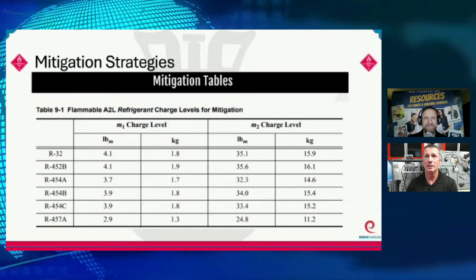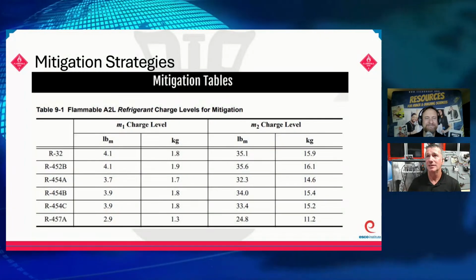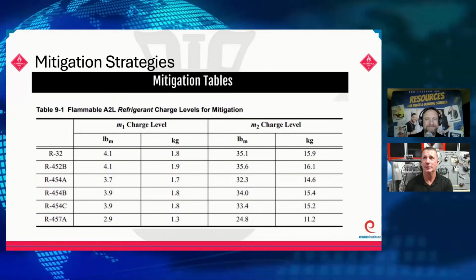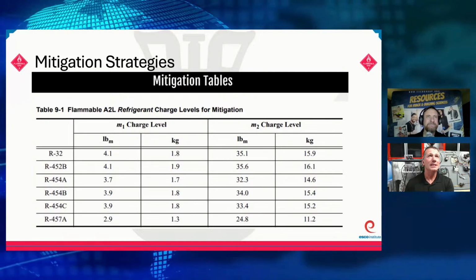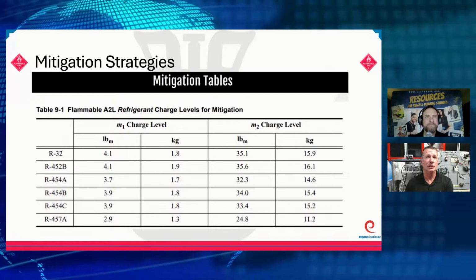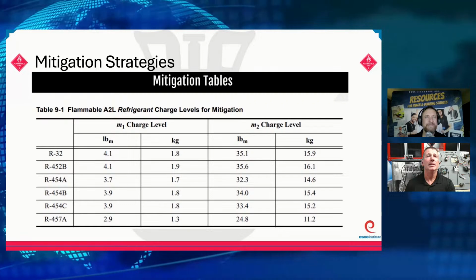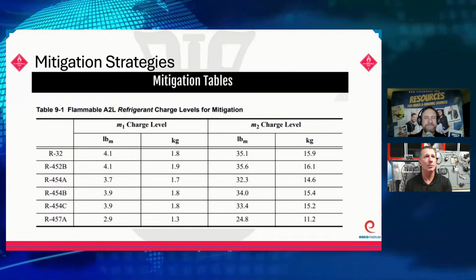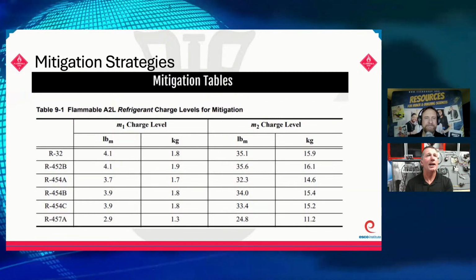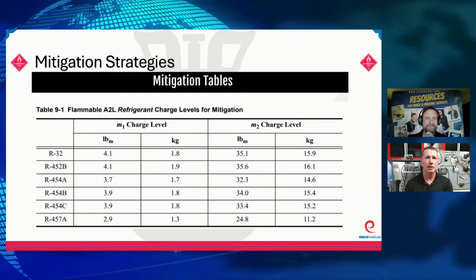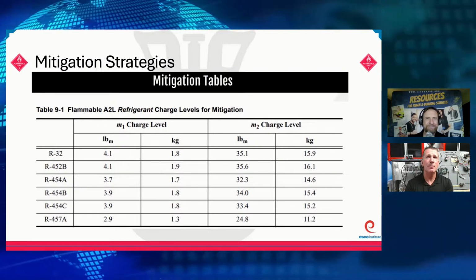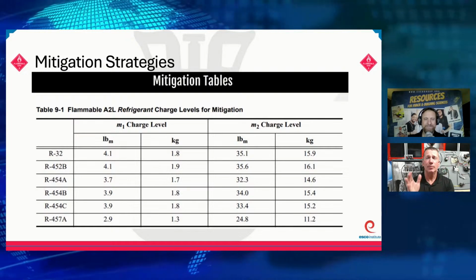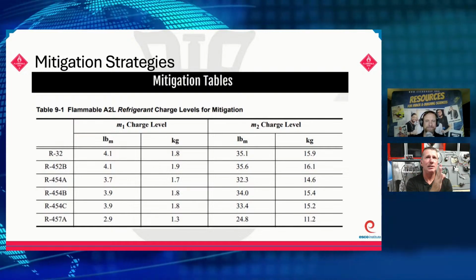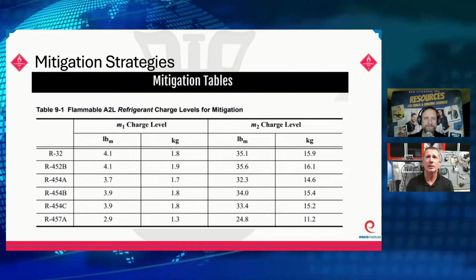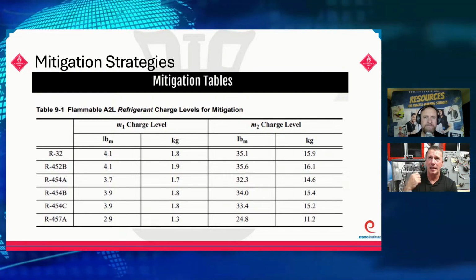We've seen a variety of different manufacturers have different controls. I want to show you a couple different ones. Like I said, Ty's got some pictures. I got some new pictures. We won't have those thrown in here for probably maybe tomorrow or a couple days. But what we're going to see as an industry, we are going to see mitigation controls similar to these in systems between 4 pounds and approximately 35 pounds. So it is 35.1 for R32 and it is 34 for R454B. Remember, it's determined by the mass of the refrigerant. So in that stage between 4 pounds and approximately 35 pounds, we're going to have mitigation controls like these.